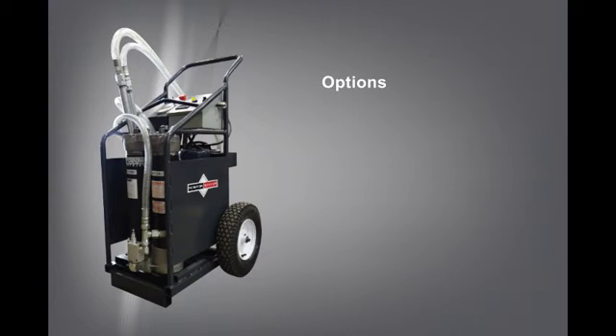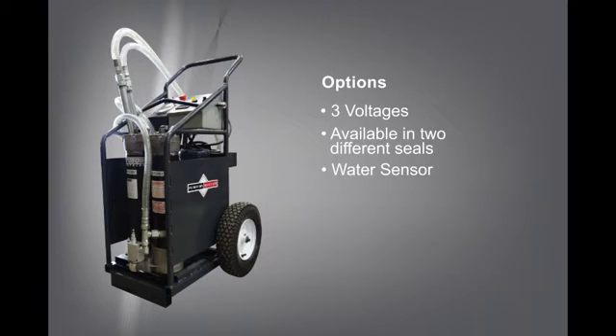The FS is available in three voltages: 120V/60Hz, 220V/60Hz, or 220V/50Hz. It is available with seal materials — BUNA for standard fluids or VITON for phosphate ester fluids. The unit can come with Schroeder's reliable TestMate Water Sensor (TWS). It comes in two pump sizes: fixed 9 gallons per minute or variable 3 to 8 gallons per minute.